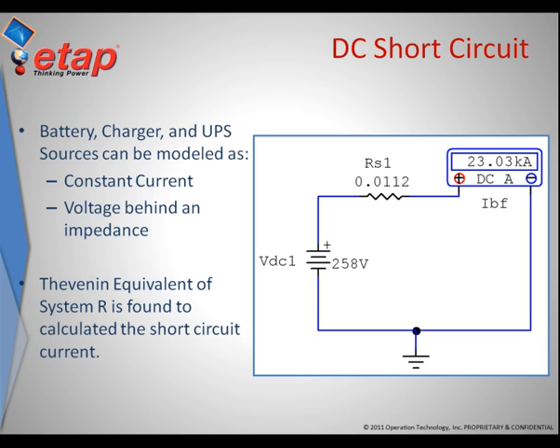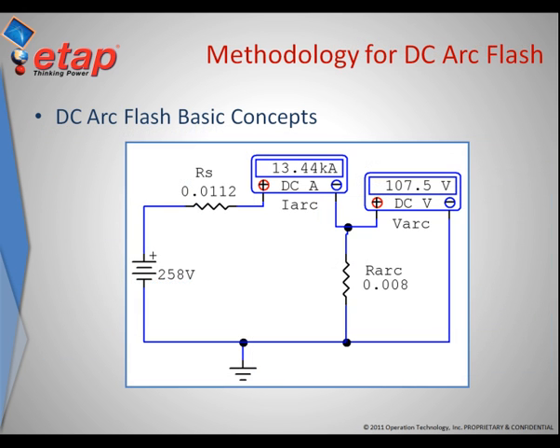Now that we have the amount of DC short circuit current which can be released for a bolted fault in the DC circuit, based on the methodology selected, we can determine the equivalent arc resistance and arc voltage drop across the arc in the event of an arc flash. The arc is modeled as an additional resistance placed in series with the system's resistance, and this new circuit will help determine the magnitude of an arc fault.